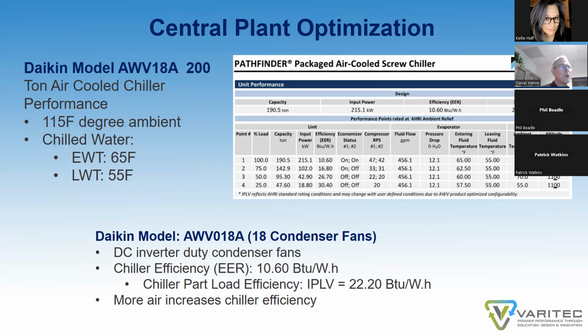You don't have to worry about a primary, secondary pumping loop. A conventional passive hydronic system would require that, because you would need to provide 44-degree chill water to a DOAS unit for adequate dehumidification, preferably probably less to get to the dew points necessary. But if you provide a DX DOAS solution, you can elevate your chill water temperature to 55 degrees, adding another layer of efficiency to a passive radiant system.